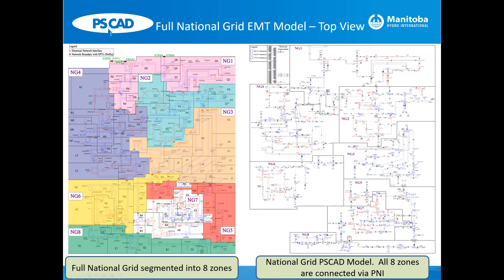PRSIM has the capability to automatically generate the network equivalent, which is essentially source impedances. These are derived through a matrix reduction technique, where the entire system nodal admittance matrix is reduced with only the buses in the study area and the boundary explicitly retained. This representation considers the power flow condition and the short circuit level at the point where you equivalenced.